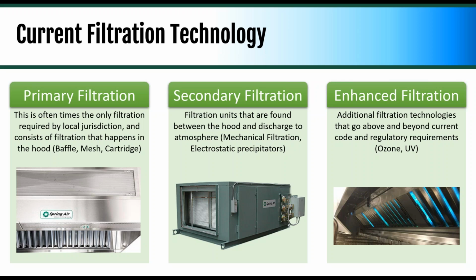When you look at current filtration technology in commercial kitchen ventilation, this is the one you see everywhere, and that's primary filtration. That's the filters that are in the hood. So in this case, we've got a hood with baffle filters. Baffles are the least efficient style of extraction, but because they're the cheapest, it's probably what you see on 80%, I'm going to say, of hoods that are in the market.